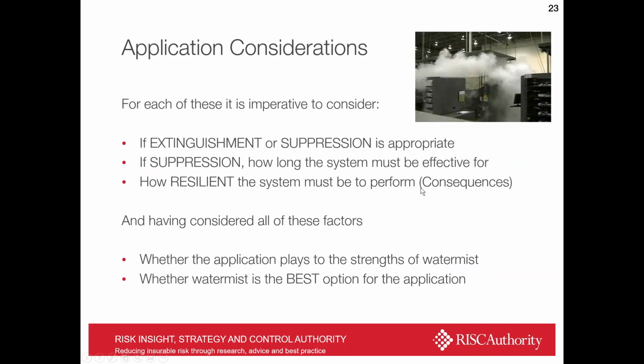Now, for each of these, it's imperative to also consider if extinguishment or suppression is appropriate, and if we talk about suppression, how long the system must be effective for. And this is generally a conversation about who's coming up to help with it, the fire service or what the secondary measures are coming to finish off the fire. And also how resilient the system must be to perform. And having considered all those factors, whether the application plays to the strengths of Watermist, and we'll talk about those in a moment, and whether Watermist is the best option for the application itself.